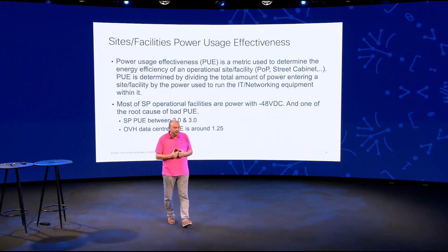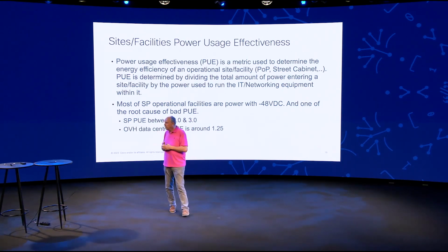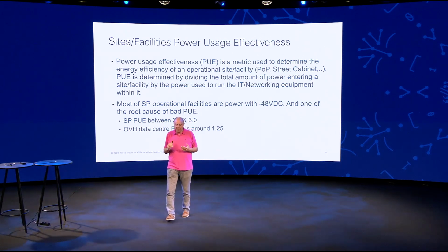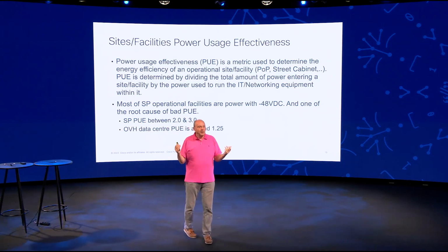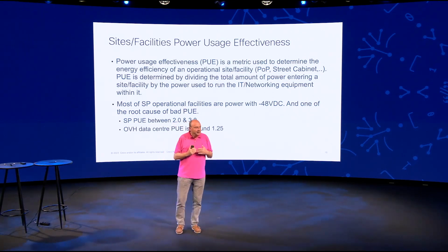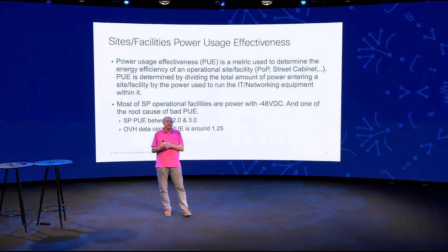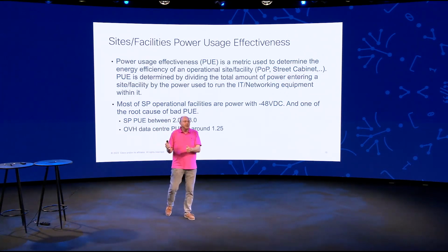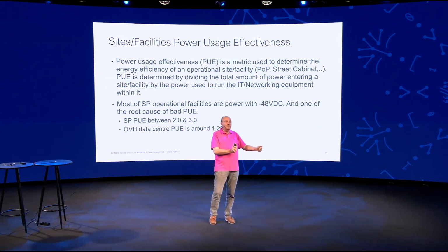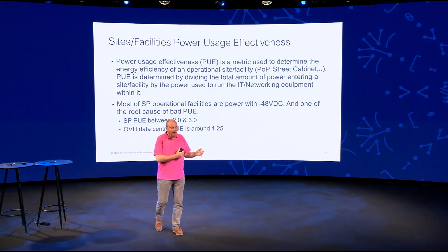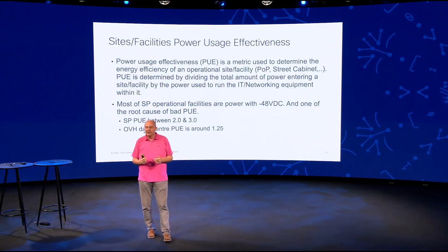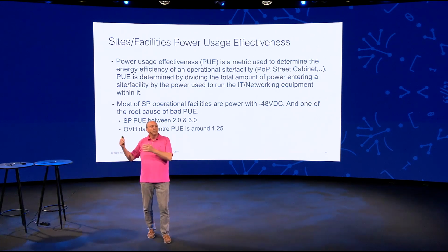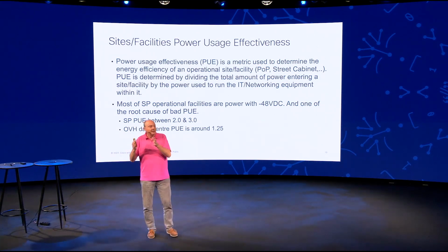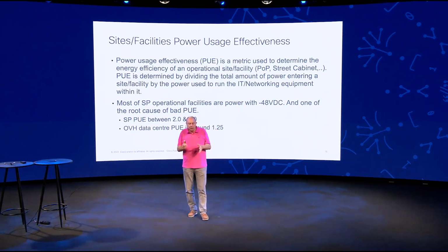If you look at an example in Europe, the company OVH and T-Loop doing the same, and they'll be the next after me. What they do is operate data centers with liquid cooling. That gives them a PUE of 1.25, meaning for every single watt consumed by the server, they're consuming 250 milliwatts for distribution and cooling, which is very low. If you look at the service provider facility or street cabinet or whatever data center in general in a service provider, the PUE is about 2.0 up to 3.0, meaning for every single watt consumed by the IT equipment or router, you consume 2 more watts to distribute and cool it.